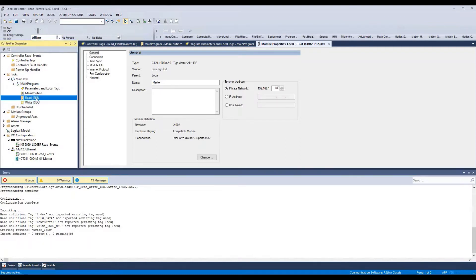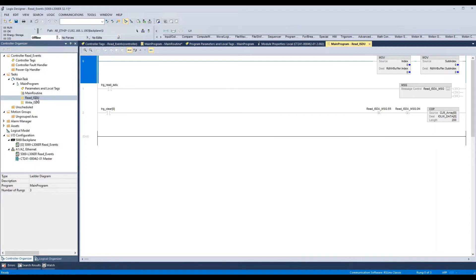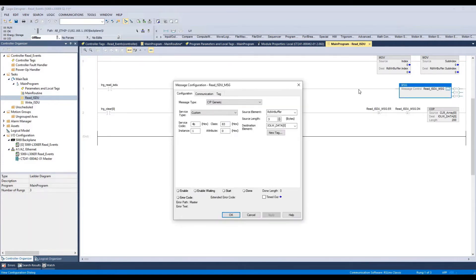If we open the Read ISDU routine, we can see the logic. In the first rung, we can see that we are storing the index and subindex to the tag Read and Write Buffer. In the second rung, we can see the message control and all the parameters: 4B for reading ISDU, instance which is the port number, the tag which will contain the index and subindex, the length of the tag, and the tag IO-Link data which will contain the data to be received when sending the ReadISDU command.